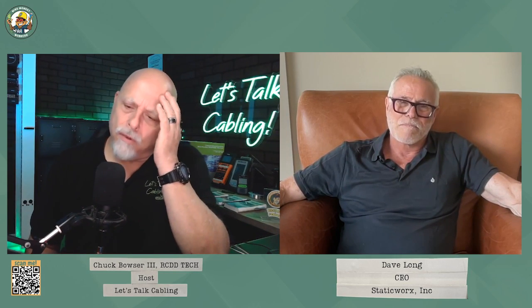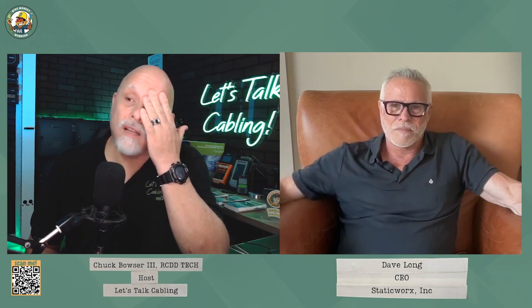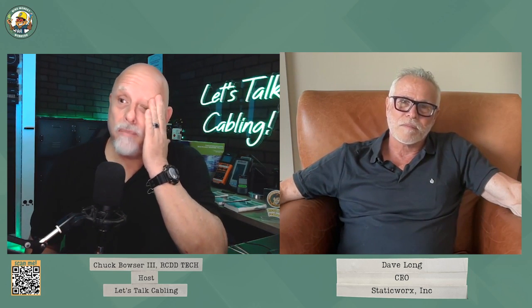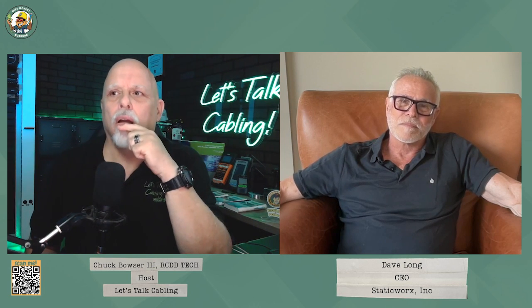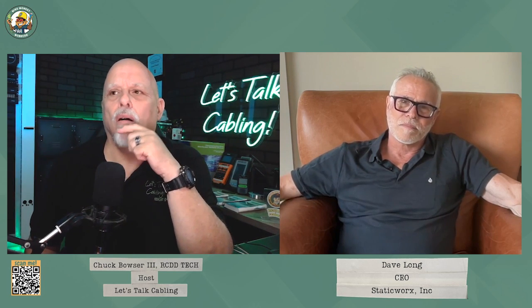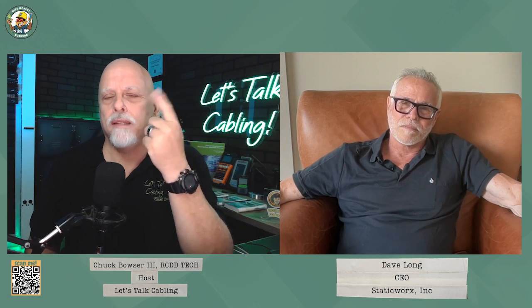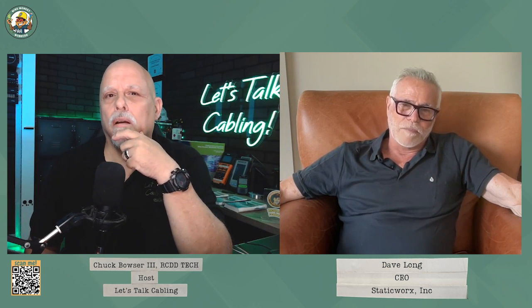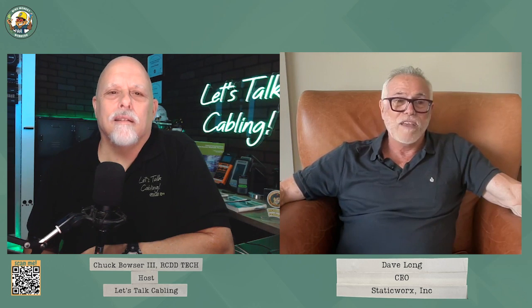So that actually brings a great question. For every 1,000 square feet, most telecom rooms are going to be 10 by 11. There are bigger ones, don't get me wrong, but most telecom rooms are small. So that sounds to me like it's just going to be one attachment point to a ground. Right. And I usually advocate two, and I'll tell you why. It's not because you need them. It's because at some point in the life of that room, someone may visit that room and wonder what that is and why it's there.